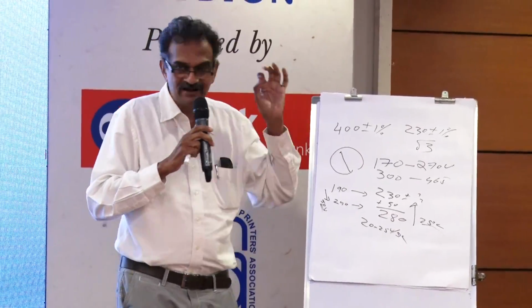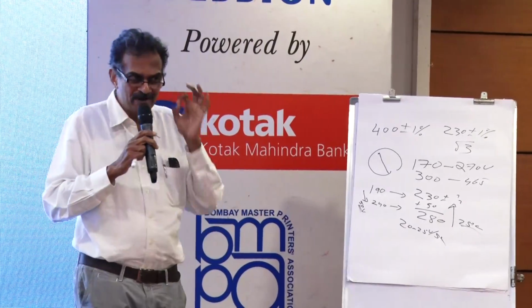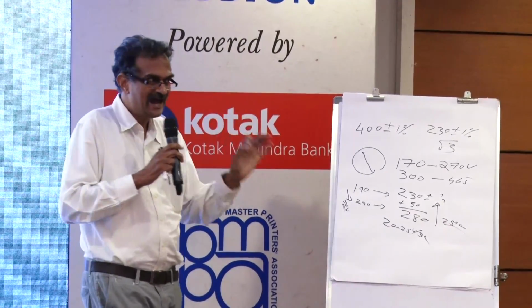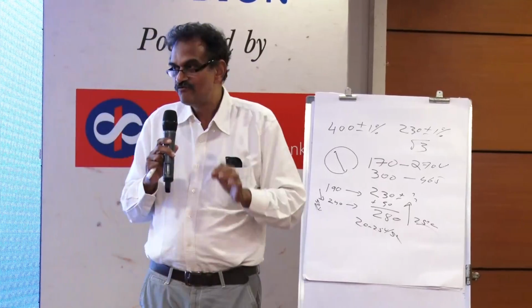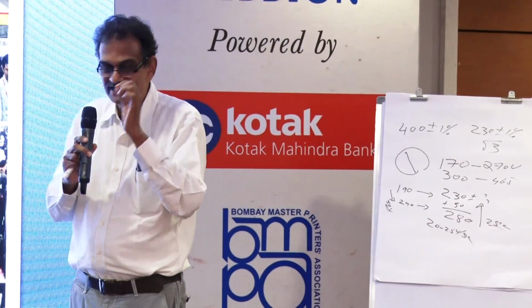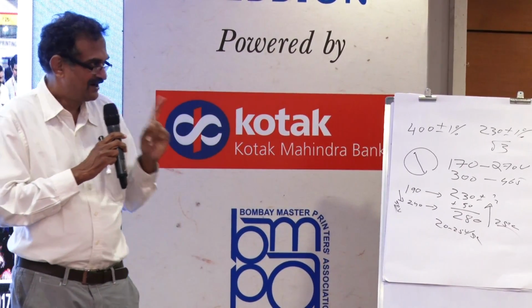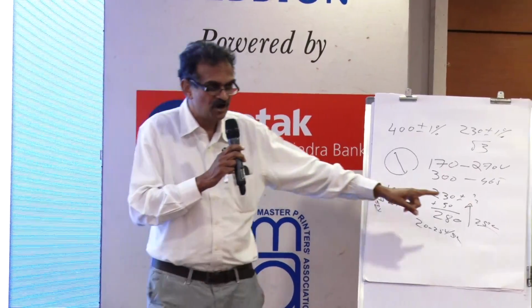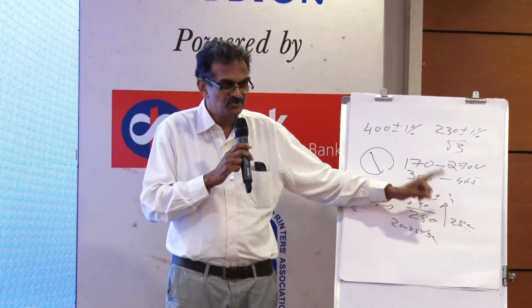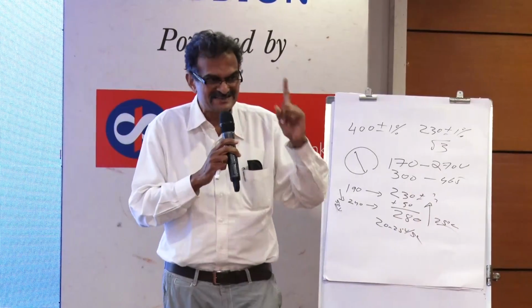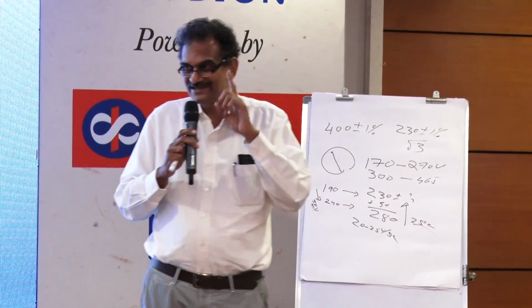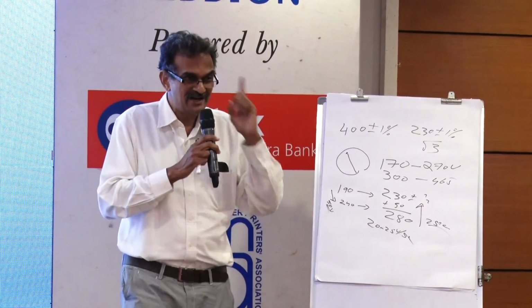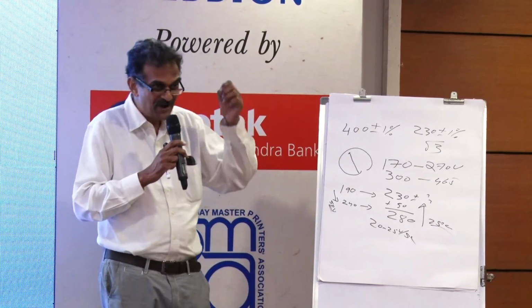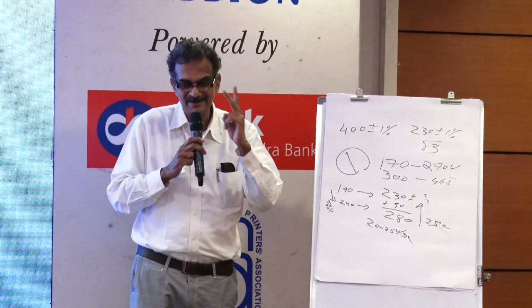But the moment they brought in electronics, all microprocessor electronics can handle this voltage change for only 1/50th of a second. You get it? And 2 seconds is how many milliseconds? 2 seconds is 2,000 milliseconds, so 1 second is 1,000 milliseconds. So you need a device that can correct within 1/50th of a second, that is 20 milliseconds.